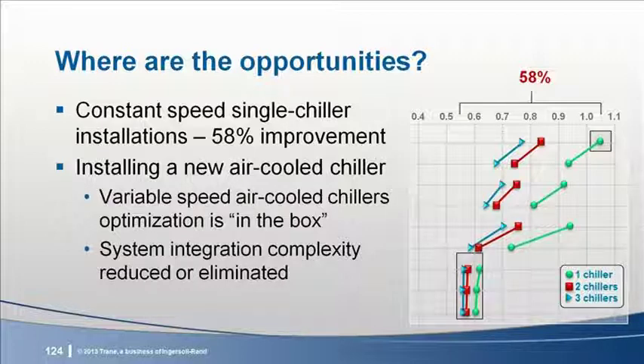The final thought I'll leave you with today is the opportunity to go all variable speed on your chiller plant anytime you're installing a new air-cooled chiller. The new generation of air-cooled chillers have variable speed compressors and condenser fans and support variable evaporator water flow. This means that all of the optimization we're discussing today for water-cooled systems is in the box, and the chiller controls handle all of this complexity already.